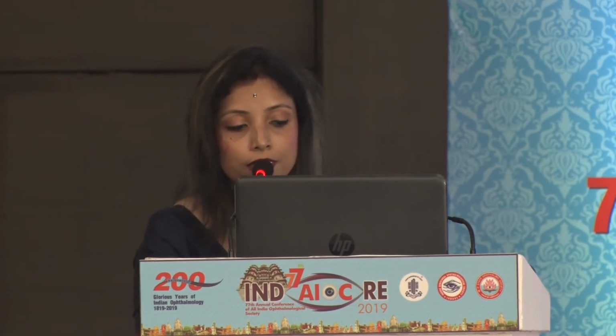This is just a glimpse of the ethylene oxide sterilizer. The instruments are individually packed. They are put inside the ETO machine. An amount of moisture is put. It is locked. The vacuum is activated. The temperature is set. And when the requisite temperature has been set, the machine will be turned off after 6 hours.